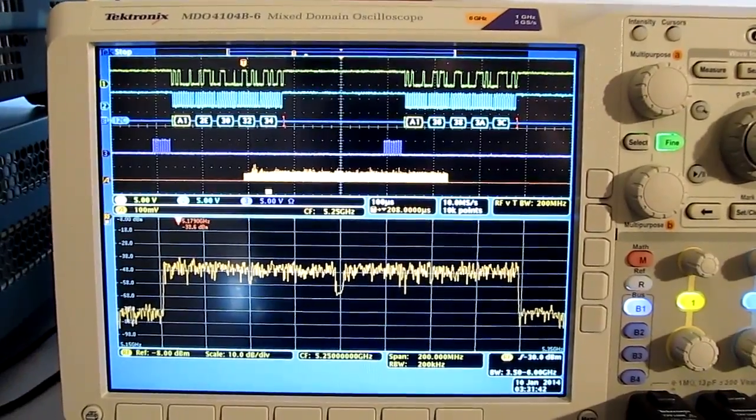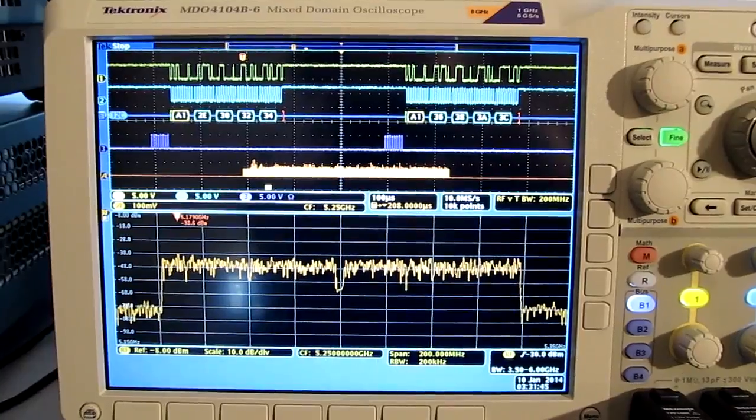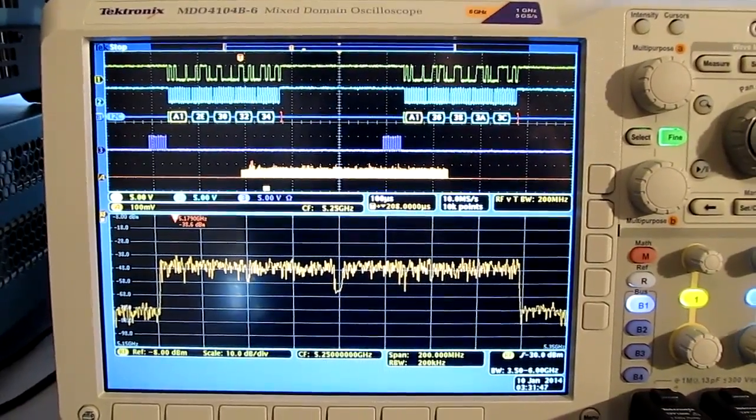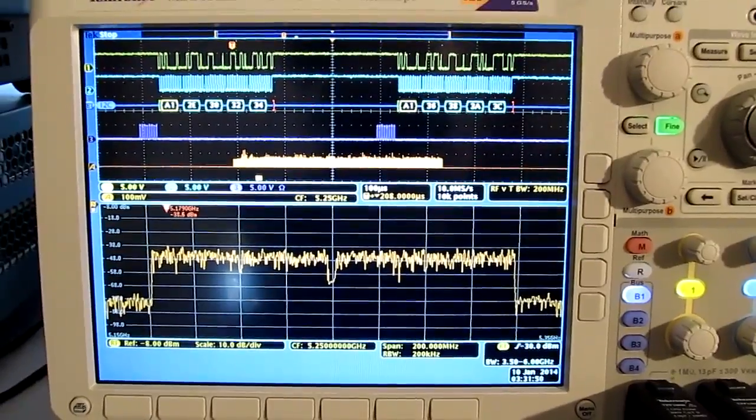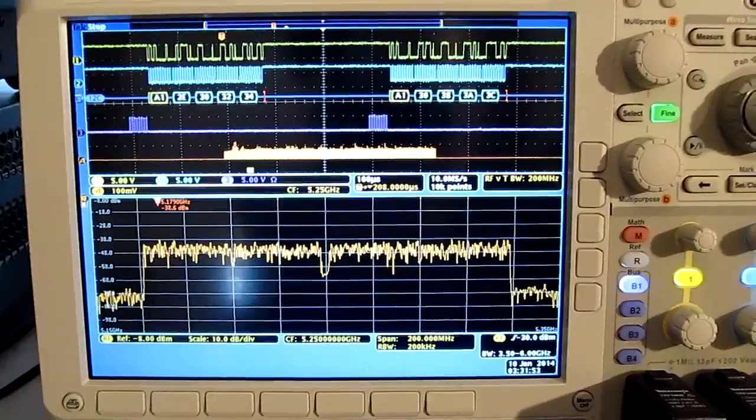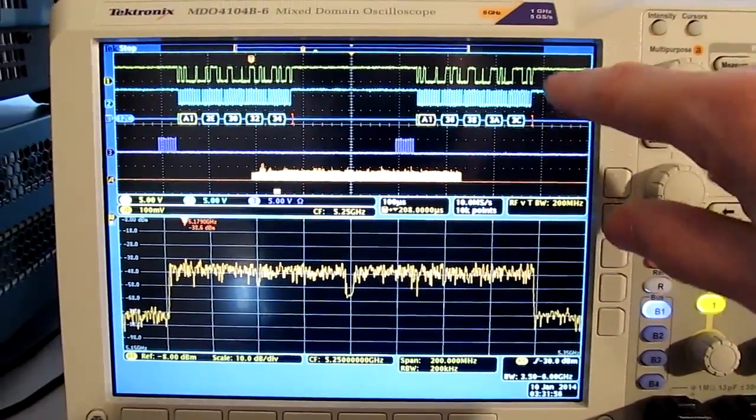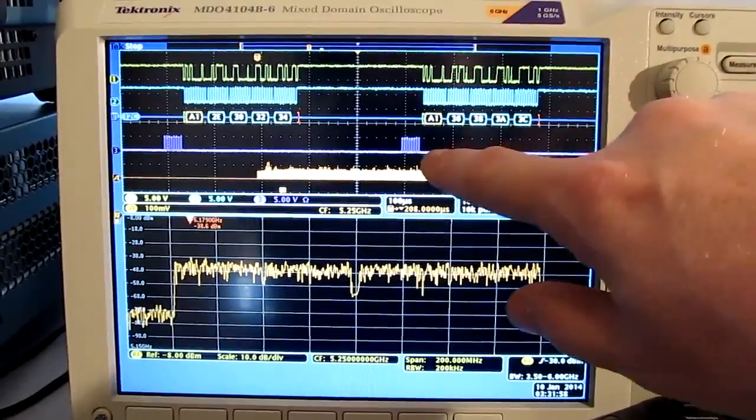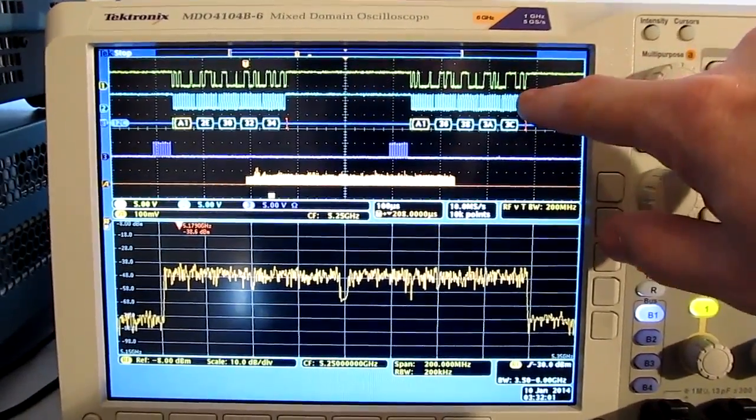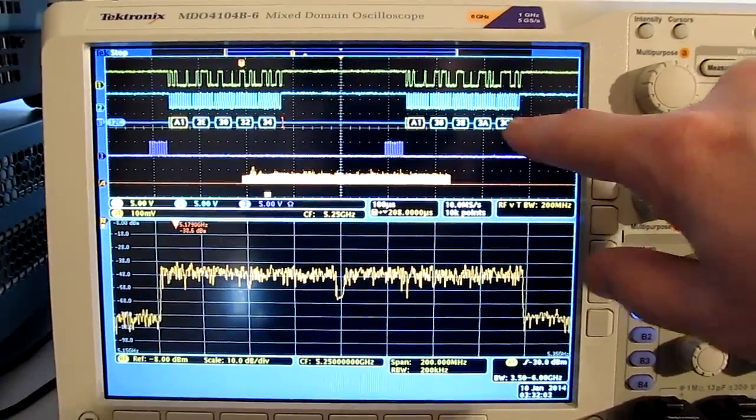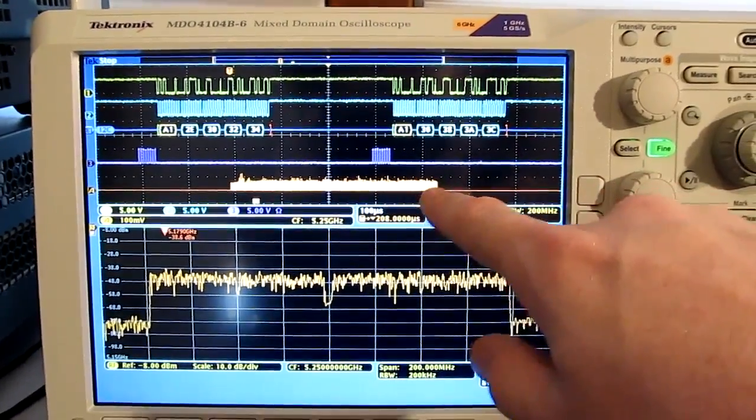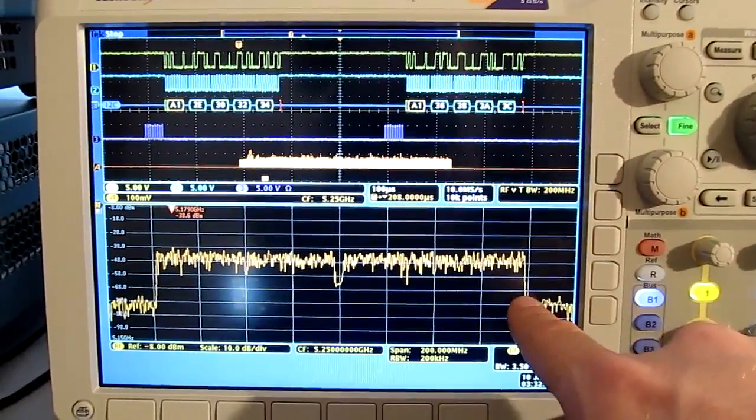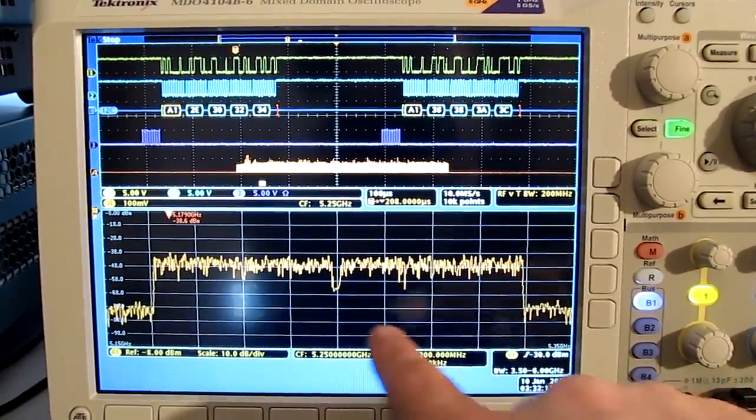One maybe practical example of using the MDO and the link to SignalVu-PC may be for integrating a wireless LAN module into a system. Here I've got a single shot capture that's looking at a couple of different signals, a little bursted clock here, an I squared C bus and the decode of that. And this display is showing me RF power versus time of a wireless LAN signal, in this case, which is at 5.25 GHz.